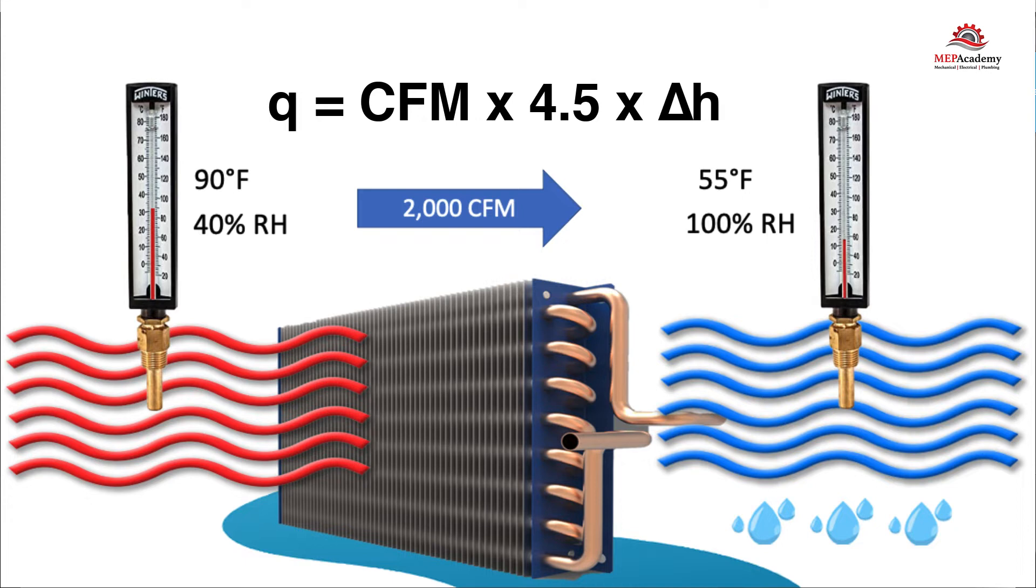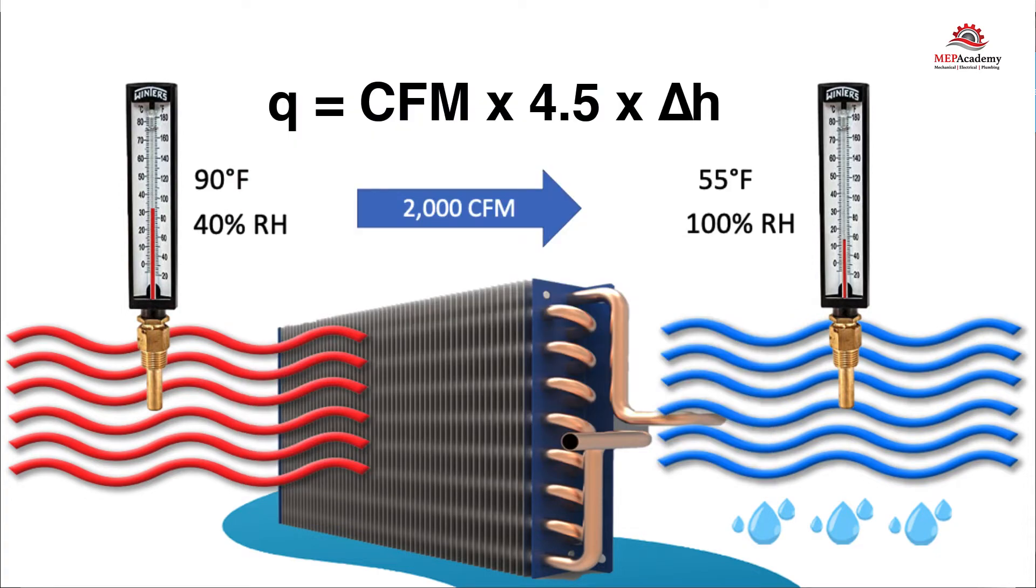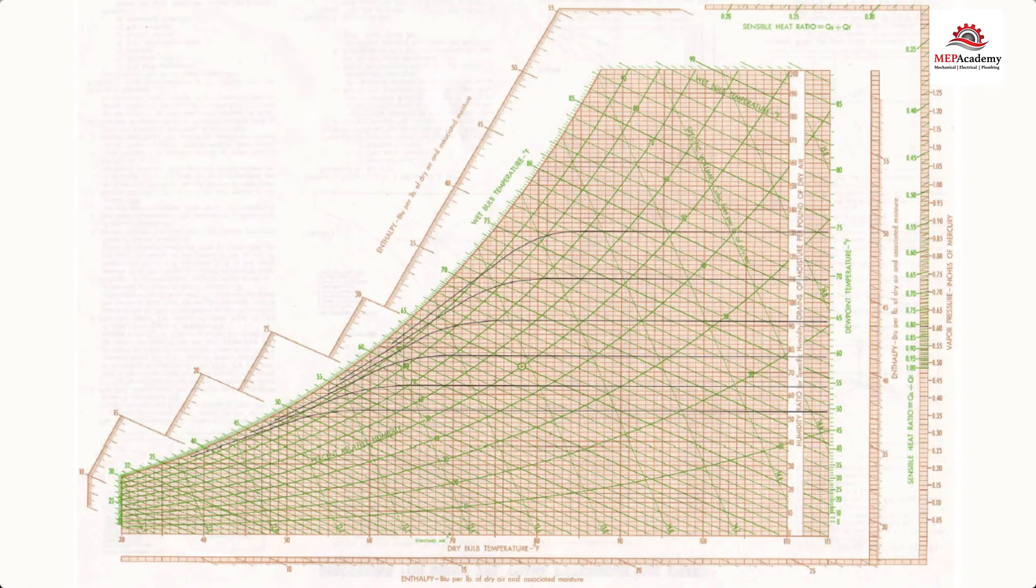Step 1 is to plot the entering and leaving air conditions on a psychrometric chart to determine the enthalpy. For the entering air conditions of 90 degrees Fahrenheit and 40% relative humidity, we enter here along the horizontal part of the chart that reflects temperature, and then we go vertically straight up.